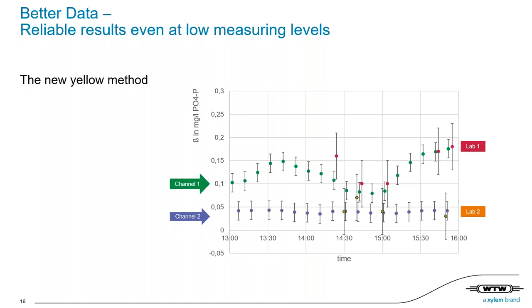As I keep mentioning, Alyza IQ PO4 provides highly accurate measurements. Here you see some data of a 2-channel Alyza and lab samples. You see in green the channel 1 of the analyzer before the precipitation and the channel 2 after the precipitation. And please note the very low concentrations, which are really accurately measured by the new analyzer. In comparison, in red and orange, you see the lab measurements. Thanks to the new technology, the new Alyza IQ yellow method is even more accurate than the lab photometric blue method, as you see by the standard deviation bars.